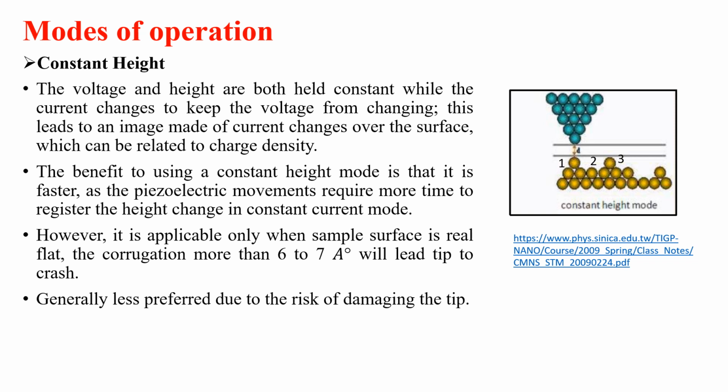So the tunneling current can be measured at each position on the sample surface, creating the topography image on the screen. The benefit of using the constant height mode is that it is faster, as the piezoelectric movement requires more time to register the height change in constant current mode. So that can be managed in this constant height mode. However, it is applicable only when the sample surface is really flat, so that the tip will not crash with the sample surface, and generally it is less preferred because there is a risk of damaging the tip as it can collide with the surface.